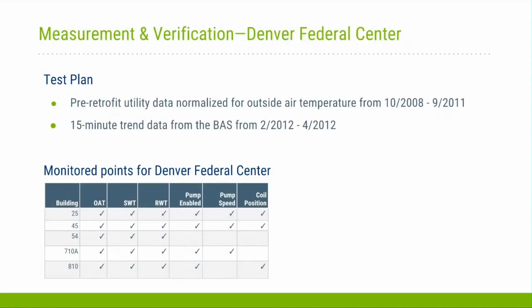Next slide. Just to give you a brief overview of the data that we collected to do this M&V process. Basically, we collected pre-retrofit utility data for all of the 5 buildings at the Denver Federal Center for a couple of years. You can see the date range, and we normalized that for the outside air temperature during those periods. And then while we were doing the study, after all of the condensing boilers had been installed, we were getting 15-minute data on all of these points listed in the little table below from the building automation system for a few months. The acronyms there are outdoor air temperature, supply water temperature, return water temperature, and then some pump conditions and coil position. So these were the points that we were collecting from the building automation system to help with the assessment.